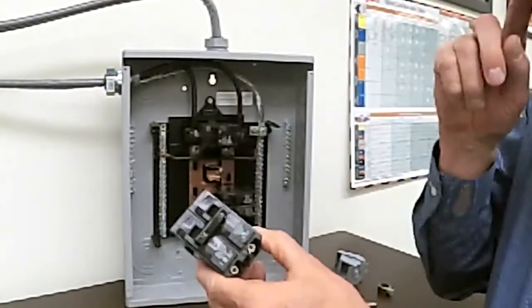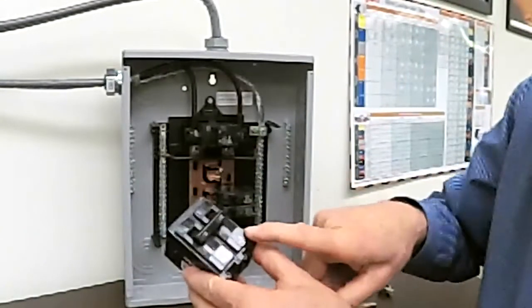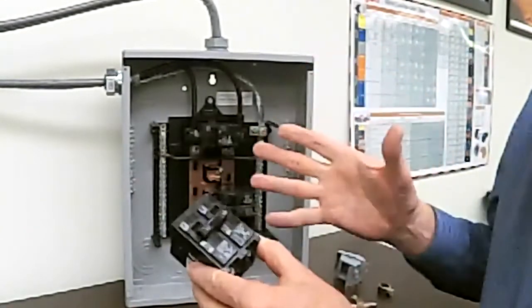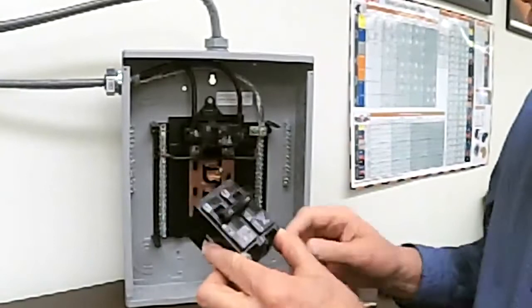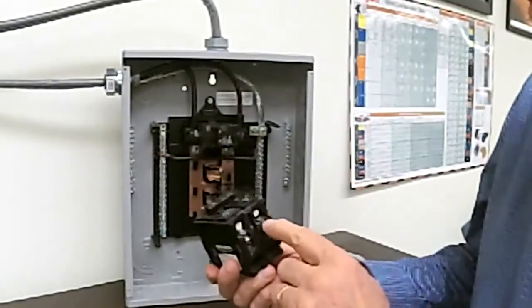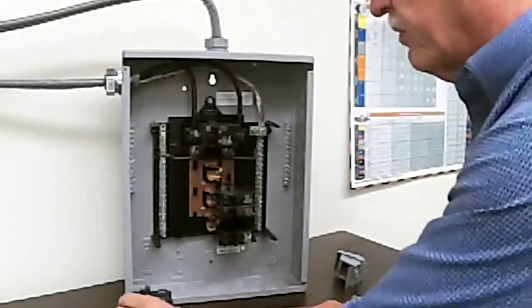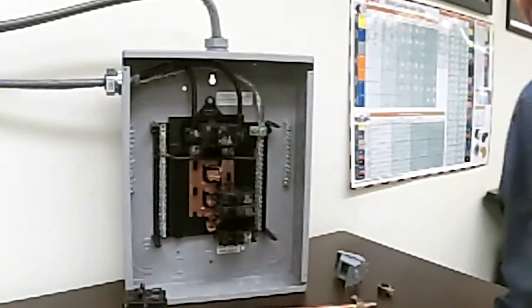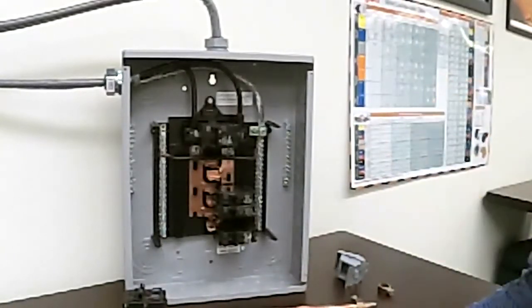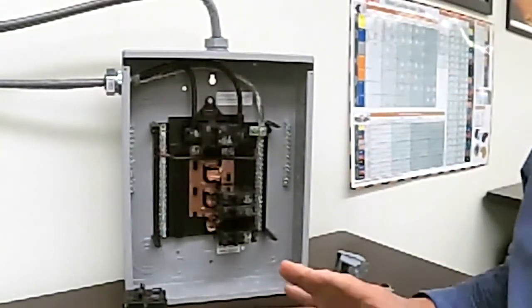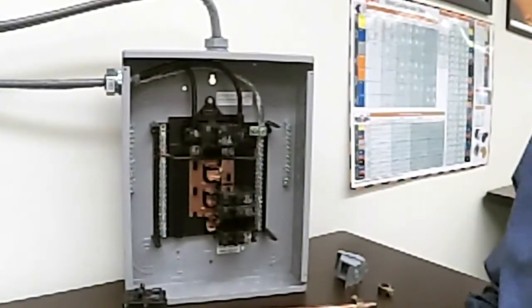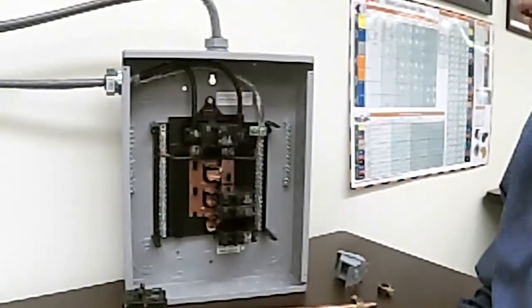35/25. This breaker is 25 inch-pounds. 25 inch-pounds or 25 pound-inches, doesn't matter, same thing. But it'll tell you there, and that's how much you tighten up this screw. That is the perfect torquing that the manufacturer wants to perfectly compress the copper conductor or aluminum conductor and follow their instruction.